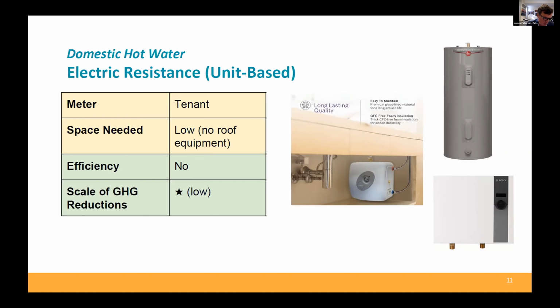So you're paying the full cost of that electricity. And if electricity is 5.4 times more expensive than gas, you're paying roughly 5 times as much for your domestic hot water as you would if it was derived from gas. So this is a difficult solution. It has been said there's only one downside to electric resistance heat, and it's cost of operation.